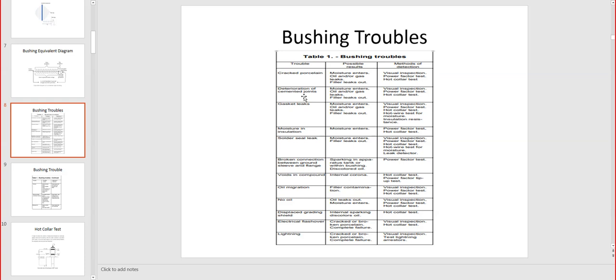Deterioration of the cemented joints, moisture again. So the worst thing that can happen initially, as initial damage, is to have moisture getting into the tank because of the bushing deterioration. As the designer, the recommendation will be to have the design done with the bushing sized larger than required, like 150%. It is a countermeasure to the deterioration.